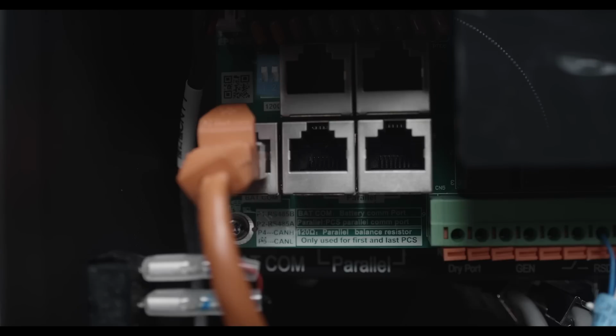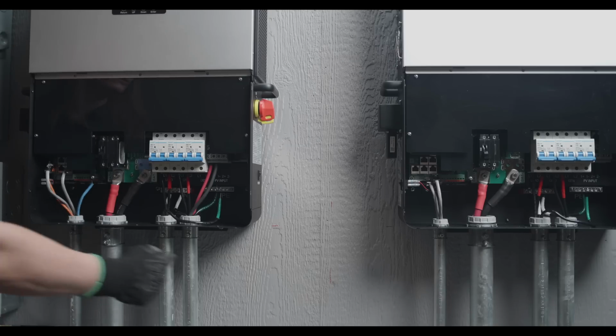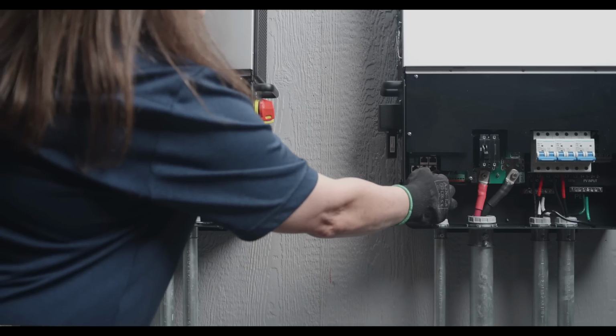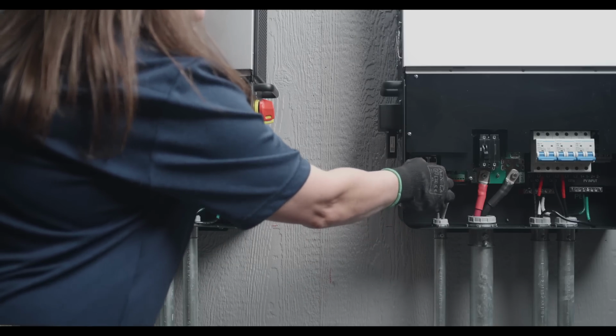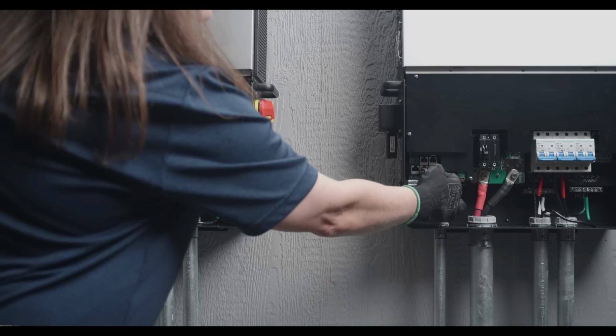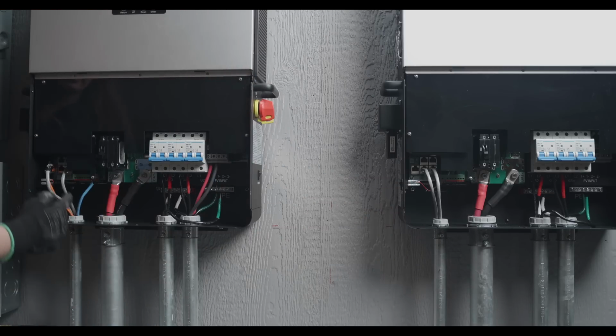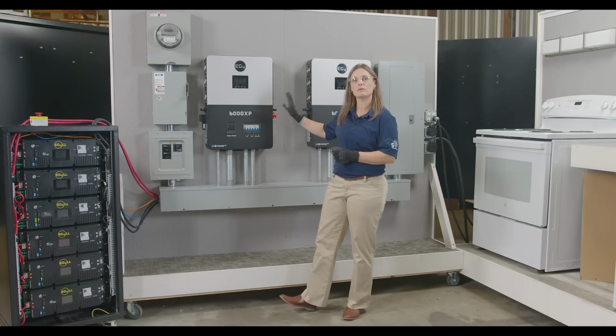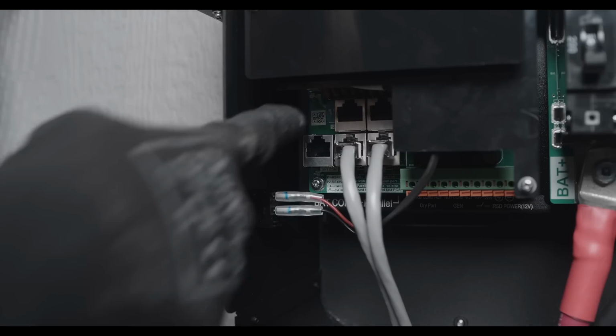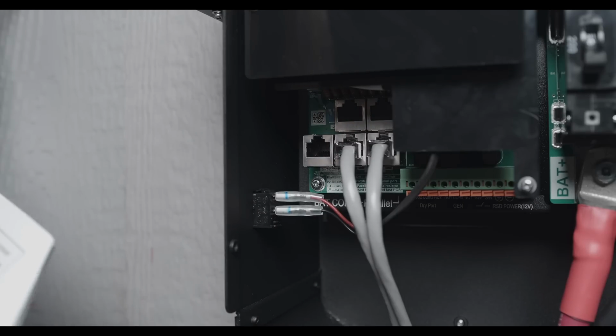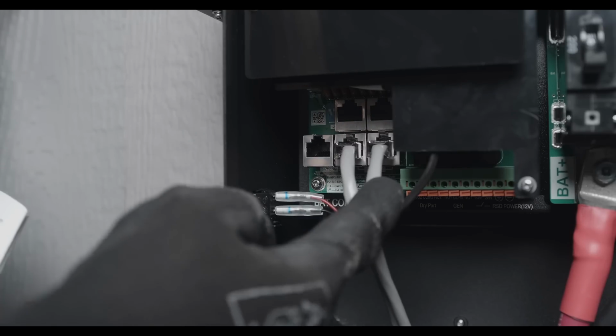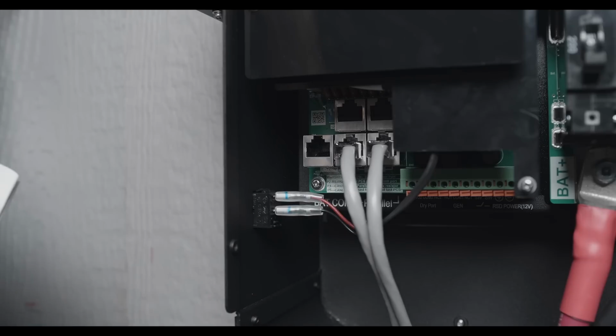For the first and last inverters in your system, set their CAN communication pins to on, both up. Every inverter in between should be set to off, both down. Connect a communications cable from the second parallel port of the inverter to the first parallel port on the next. Keep going until you reach the last inverter. Then loop the cable back to the first or master inverter's first parallel port. With 2 units like we have here today, we will set both pins to on. Connect them in parallel using 2 cables, one for the outside parallel ports and another for the inside parallel ports.